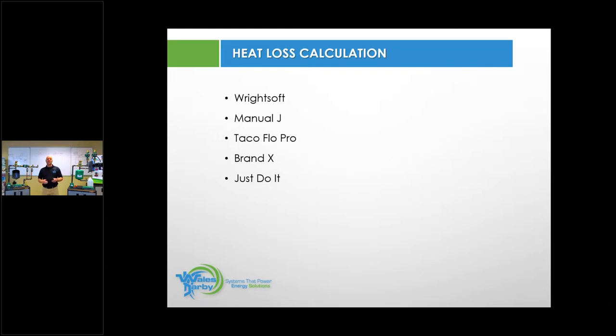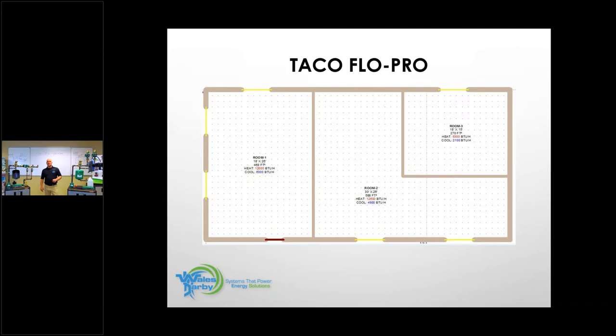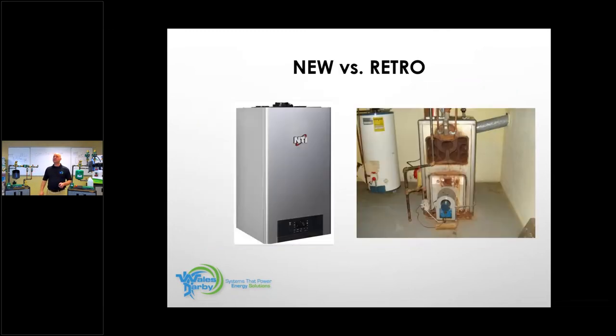And the reason I say that is because the majority of the boilers in our footprint are oversized. And the reality is, 50% of those that are oversized are probably grossly oversized. We'll talk more about oversizing and undersizing boilers and what that does to a system in general as we go along. So that's just an example of a Taco FlowPro. It's a click and drag type heat load, gives you heating and cooling loads, but again, we don't care what heat loss calculator you use. We just really would like it if you used one to give the homeowner the right job.